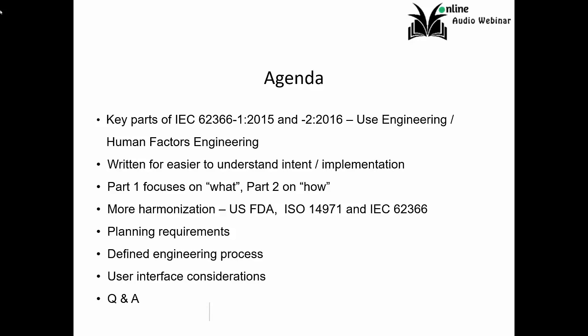So the goal was to harmonize this also with the risk document ISO 14971. If you read it, the 62366, you will find a lot of references to 14971 and similar terminology. So they're used in conjunction. And both documents are to be used in the design of product. So that's the important factor to keep in mind. They're used in design to reflect increasing the safety of the use of product. So the goal is to use it during the design and development. Now, ISO 14971 is used 100% of the time with new products and major changes to existing products.